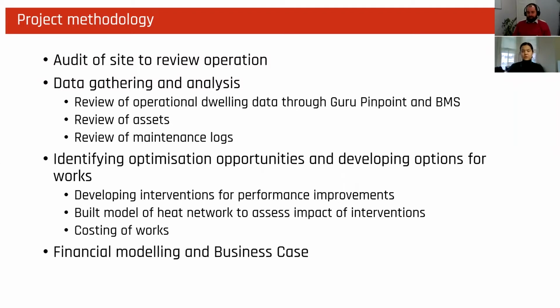And then through that process, we could identify optimisation opportunities by building an actual model of the heat network, and then coming up with a series of interventions and testing those interventions on the heat network, so that we could objectively see what impact that would have on, for example, heat losses on the system or the performance of the heat generating equipment.